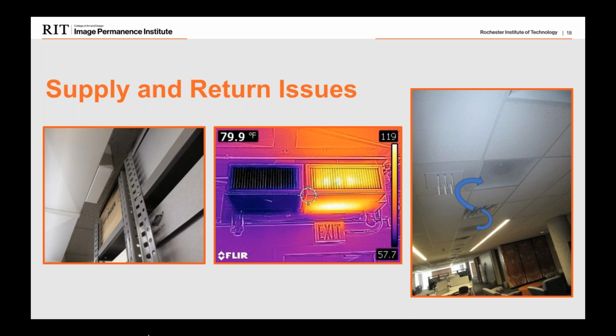On the return side, you can starve your unit of air. Air will not get to the unit. It'll impede the airflow and cause the unit to run inefficiently. On the supply side, if you put boxes too close in front of the supply diffuser, less than 12 to 18 inches, there is a possibility the air will not mix properly when it comes out of the vent. And if you lose a reheat or the heating coil goes down, you could have very cool air with a high moisture content blowing right on your collection materials. We've seen instances where that has caused mold on a collection. We'll give an example of that in a few slides.